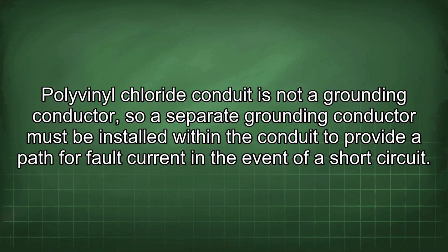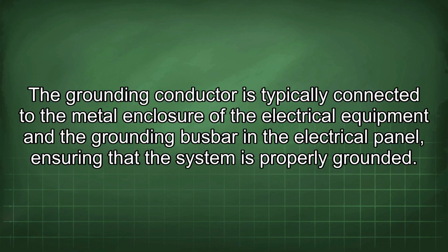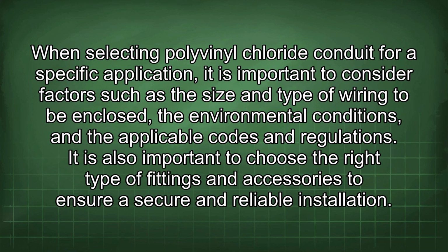Polyvinyl chloride conduit is not a grounding conductor, so a separate grounding conductor must be installed within the conduit to provide a path for fault current in the event of a short circuit. The grounding conductor is typically connected to the metal enclosure of the electrical equipment and the grounding busbar in the electrical panel, ensuring that the system is properly grounded. When selecting polyvinyl chloride conduit for a specific application, it is important to consider factors such as the size and type of wiring to be enclosed, the environmental conditions, and the applicable codes and regulations.